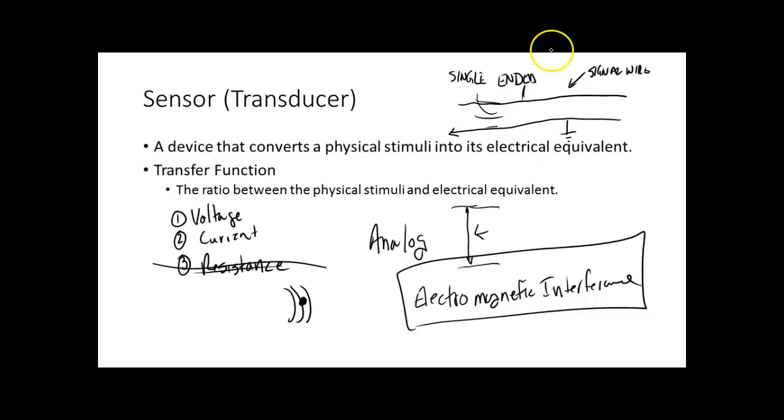So what we started doing, of course, was encapsulating this in a shield. And then we would take the shield on one end and connect it to ground. And shields are not supposed to be connected to ground on both sides. Anybody know why? Makes them a current carrier. That's exactly right. It's almost impossible to keep two pieces of equipment at the exact ground potential over distance.